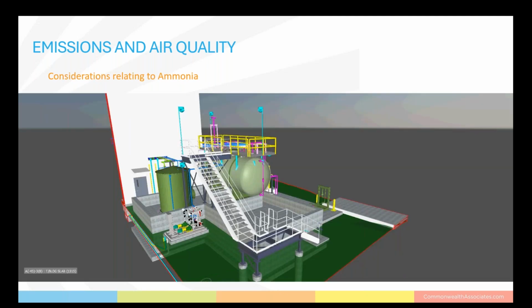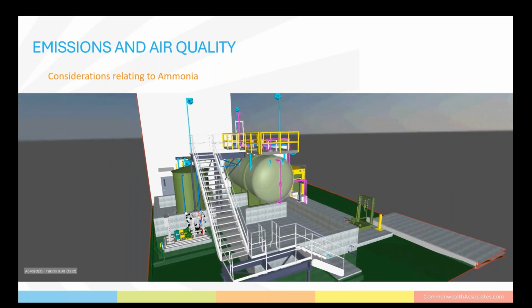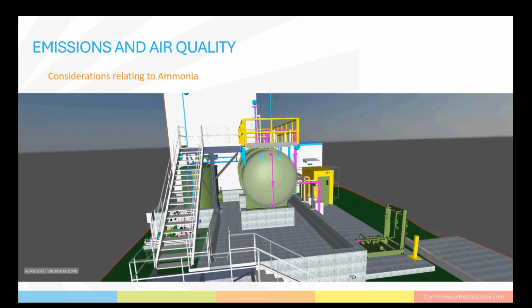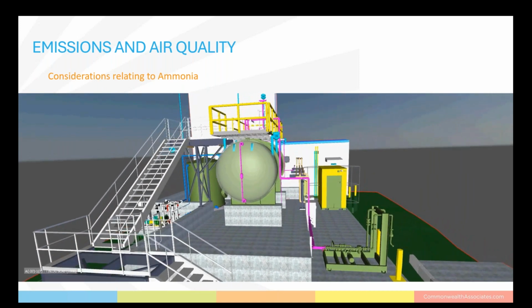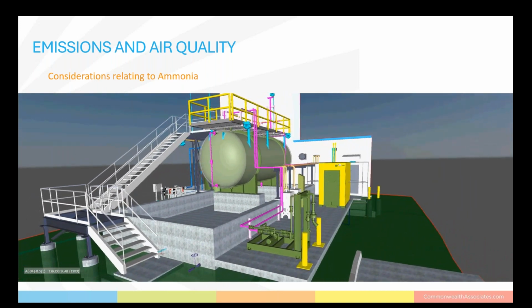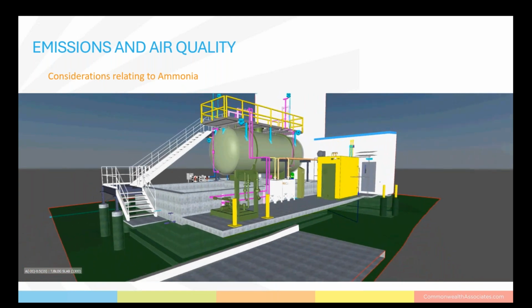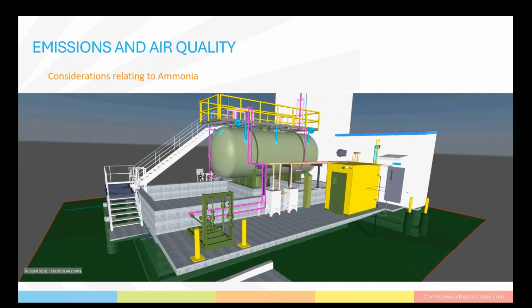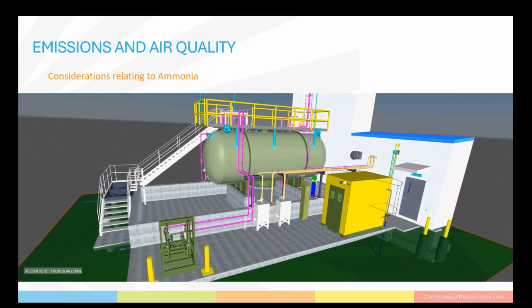Ammonia solution is considered more efficient than urea and safer than anhydrous ammonia. What we see here is a 3D model of ammonia storage and handling area, highlighting many of the things that we need to consider. The ammonia unloading skid sits on a pad outside the containment area, will require truck access and some form of spill protection at the truck.